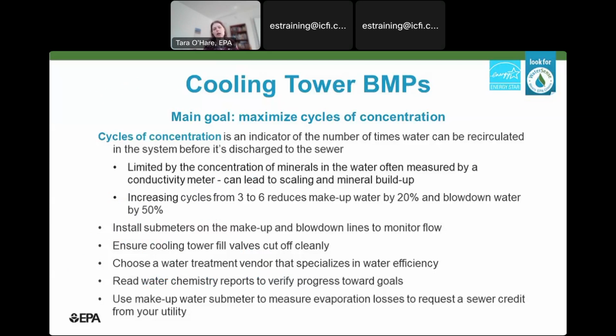So it's often limited by the actual concentration of minerals in the water, and it can be measured by a conductivity meter. If there's too much minerals building up in the water, it can lead to scaling and mineral buildup, which can wreck the system and cause a lot of damage, and cooling towers are not cheap. They're a significant cost expenditure, so you want to make sure that it's in very ideal operating conditions. So one thing to keep in mind is that increasing the cycles of concentration from 3 to 6 reduces the water that's needed to replenish the system by 20% and the water that's sent down the sewer by 50%. So it can be a really easy way to really save a lot of water in your system.